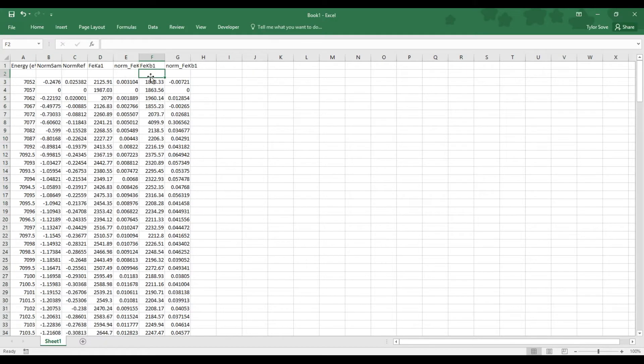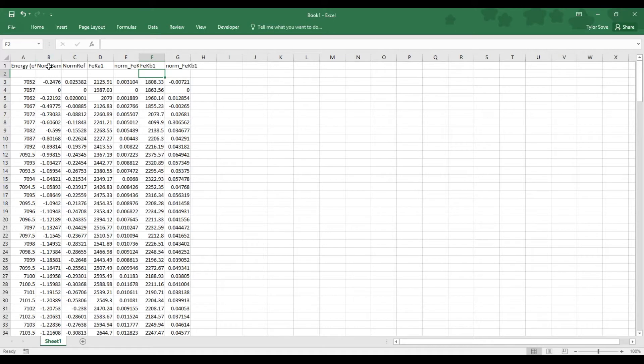Now we may not know this beforehand, but your sample might be too thick, too thin, or not have the right concentration to be detected by absorption mode. And absorption mode deals with Norm Sample and Norm Ref.